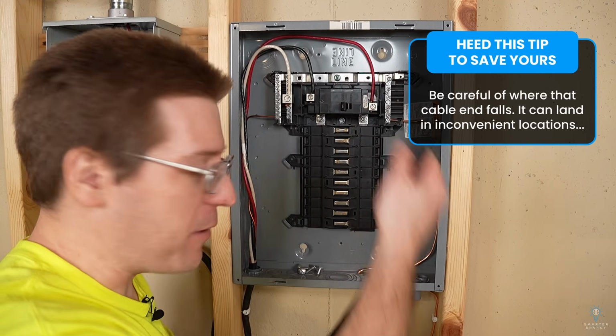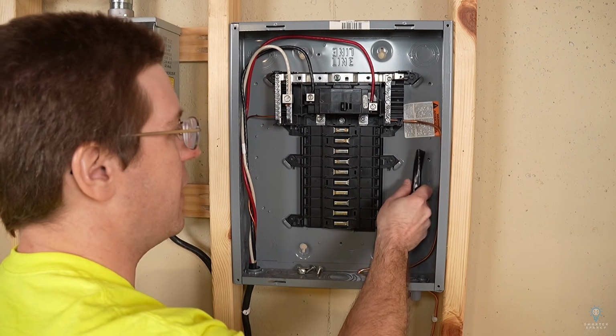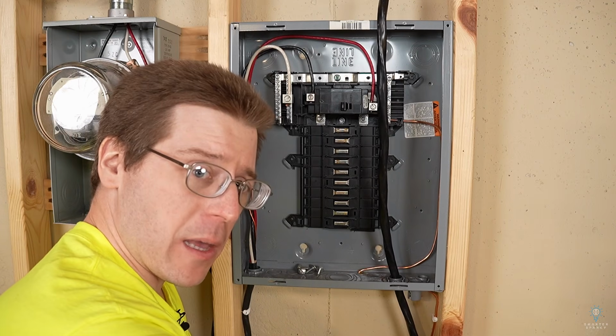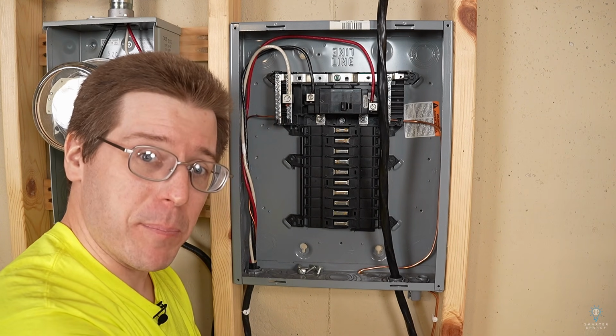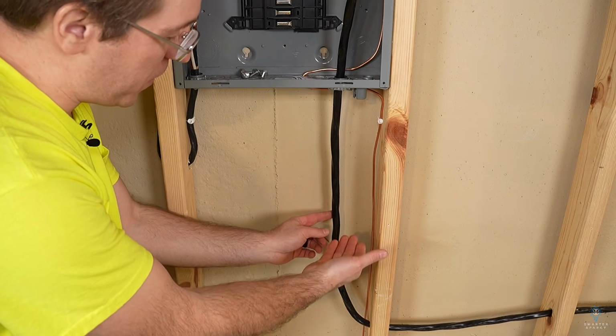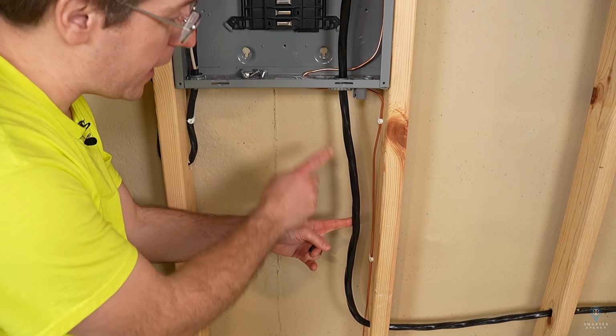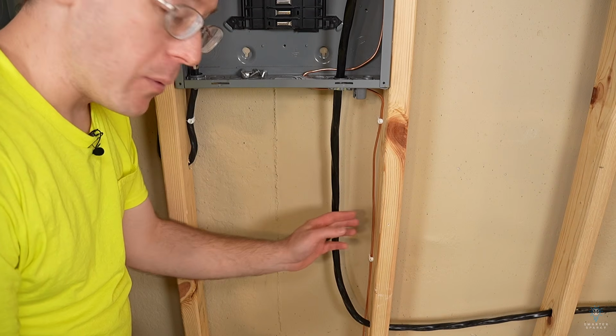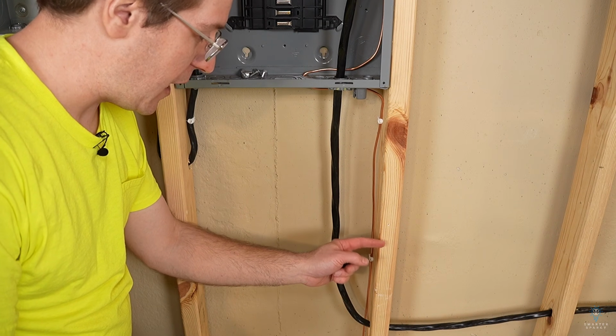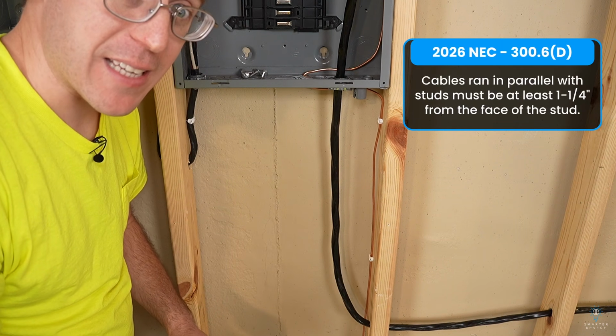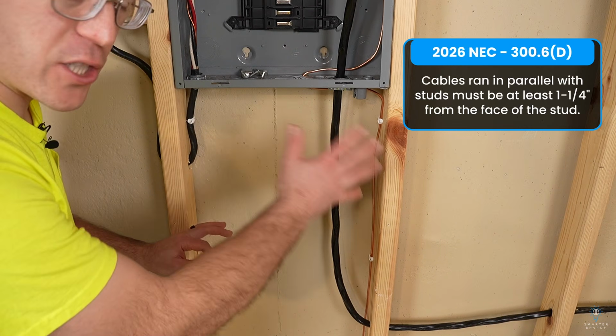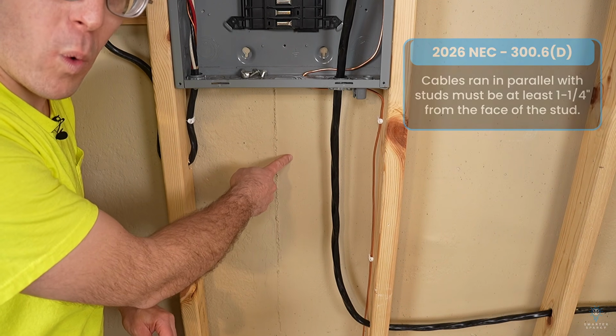Whew. And now we can feed that up through the connector and into the panel. Same thing that we did with the sub panel. I'm gonna go ahead and staple this right now. So we have to staple within 12 inches of it leaving the panel because we do have a clamp there. And we need to make sure the wire is no closer than 1.25 inches from the front or the back side of the stud. Again, in my situation here, we're pretending this concrete wall is not here.